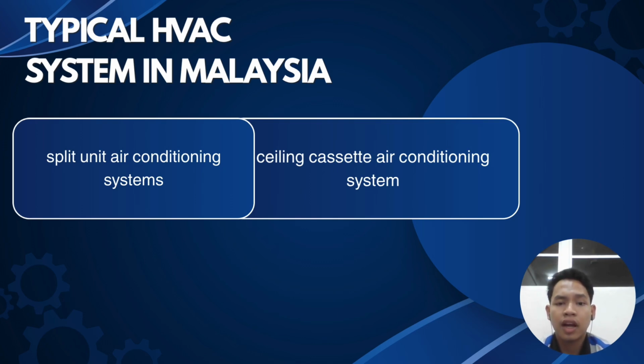Conversely, ceiling cassette units are integrated directly into the ceiling framework. They distribute conditioned air in multiple directions simultaneously, providing a much more uniform temperature gradient across a wide area. While ceiling cassettes require a higher upfront investment and ceiling structural work, they are far more efficient for wide, open-concept spaces such as community halls, open offices, and surau, where consistent cooling for a larger crowd is required.